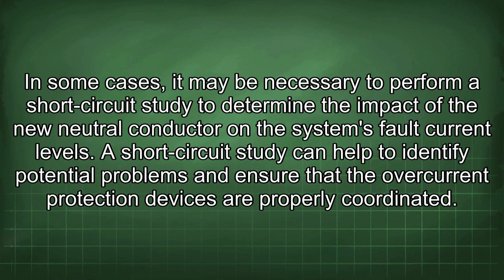In some cases, it may be necessary to perform a short-circuit study to determine the impact of the new neutral conductor on the system's fault current levels. A short-circuit study can help to identify potential problems and ensure that the overcurrent protection devices are properly coordinated.